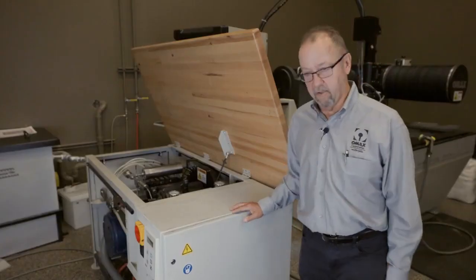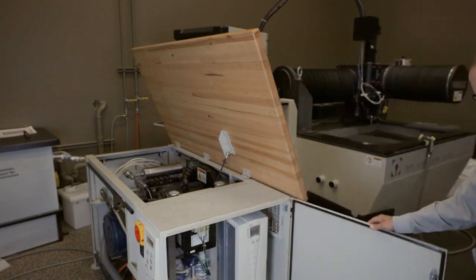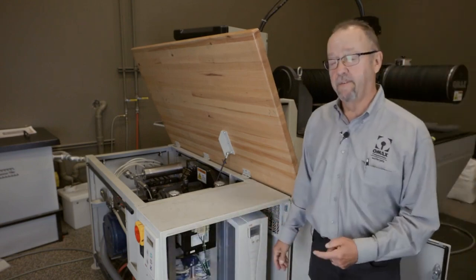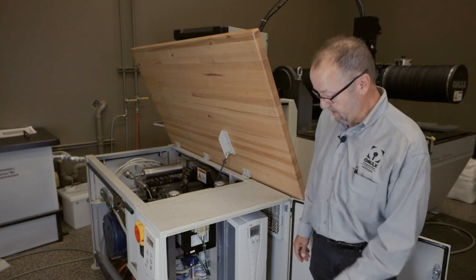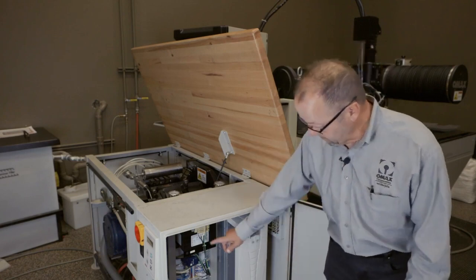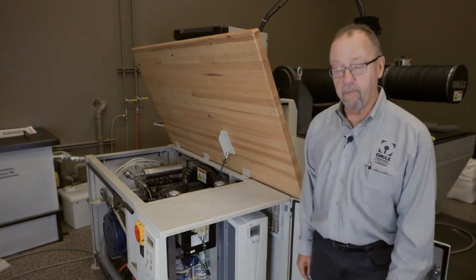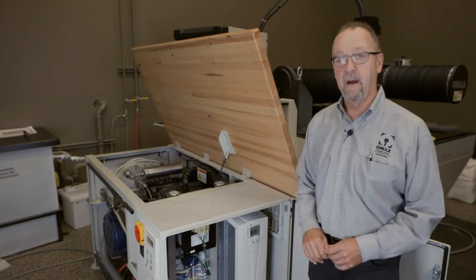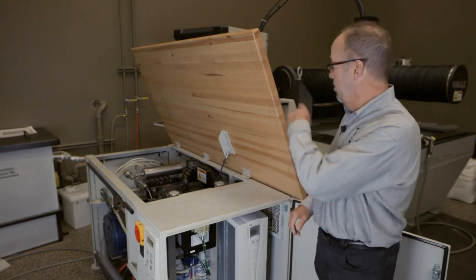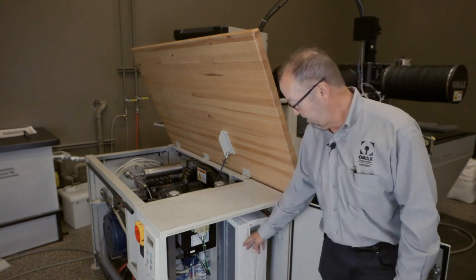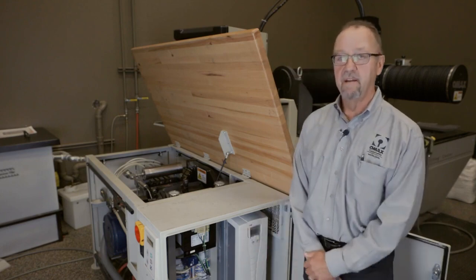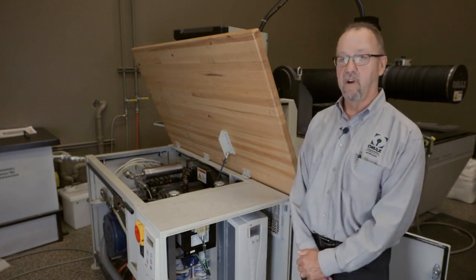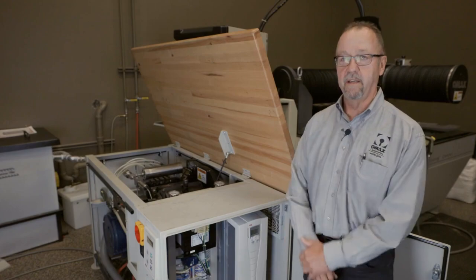Okay, this is our electrical cabinet. Again, 460 to 480 3-phase power comes into here to drive the motor. We use a step-down transformer here that supplies power and signaling to our controller. And we use a real durable ABB variable frequency drive. Again, we control the pressure by controlling the RPM.